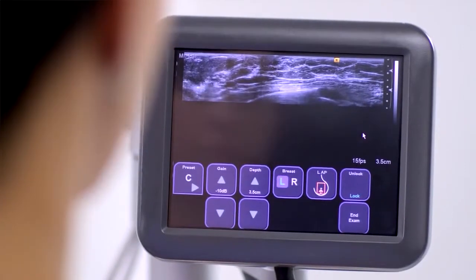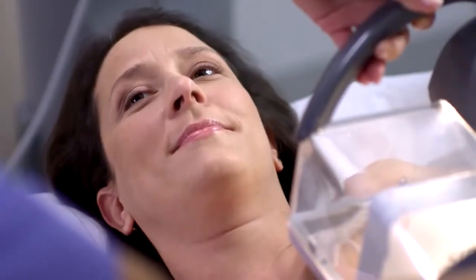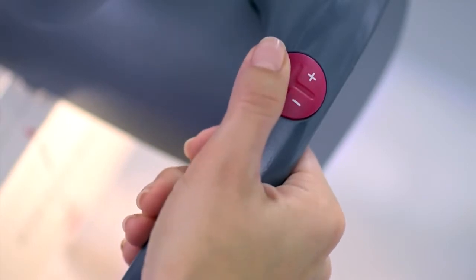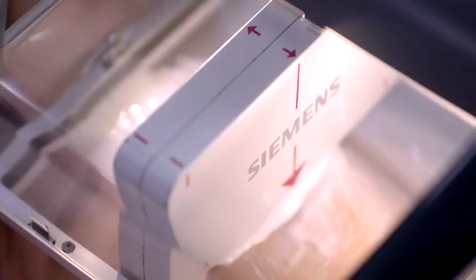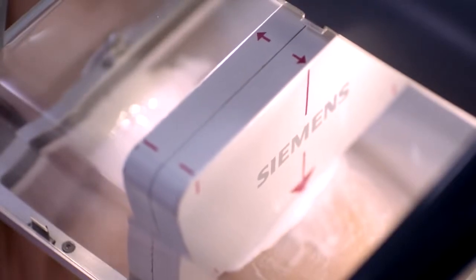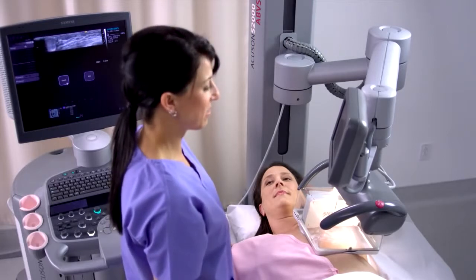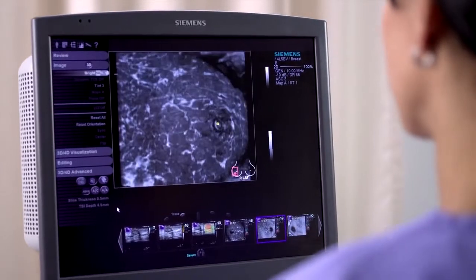During positioning, the operator can easily view the ultrasound image to ensure proper contact while simultaneously focusing on the patient. The one-button locking mechanism addresses the common problem of repetitive stress injuries and allows more accurate, hands-free scanning. Each 60-second acquisition produces a full volume with up to 400 frames, and because image acquisition is automated, results are consistent, reproducible, and independent of the user.